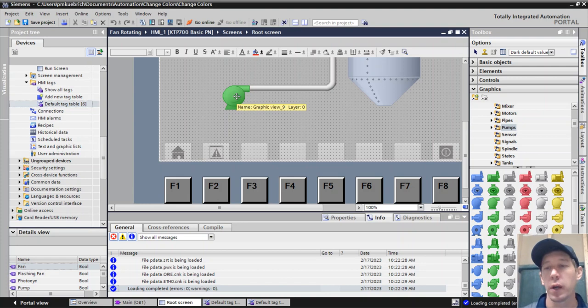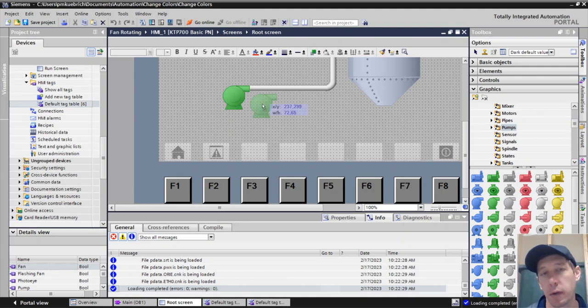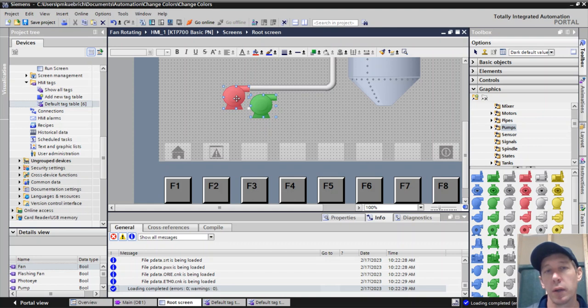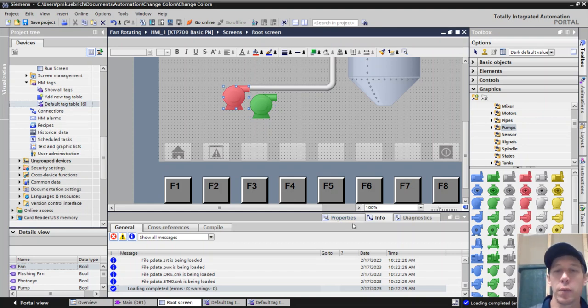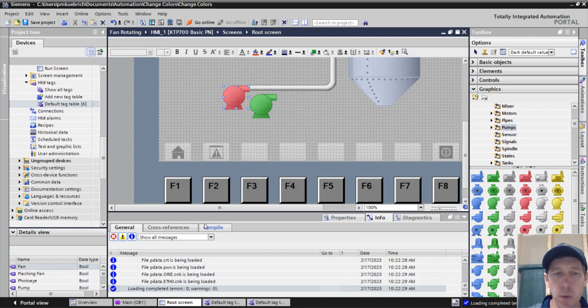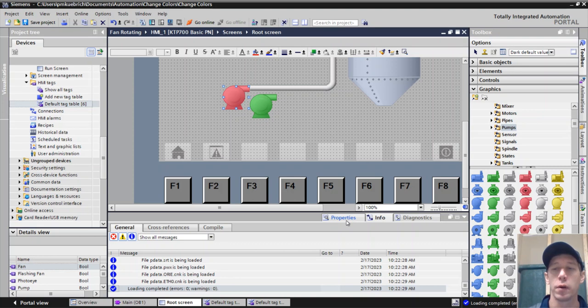A lot of plants will have gray means off and everything's good, and then green is on and everything's good. And then red might only appear. You might put gray at the bottom and then green, and then red only appear when there's a fault or something. You just have to figure out what your fault bit is and tie it to that to only appear when your fault bit is true or active.